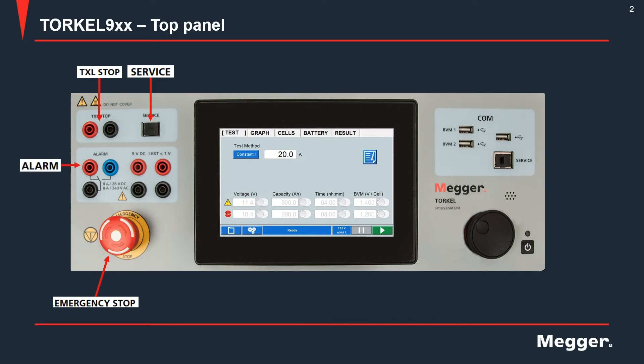There's a provision to connect an external alarm device. The alarm device will sound alarms in some situations, for example when a warning limit is exceeded or when the battery voltage is too high.